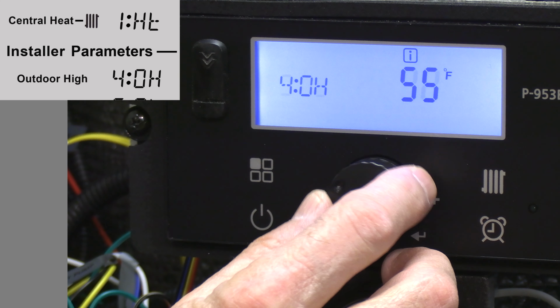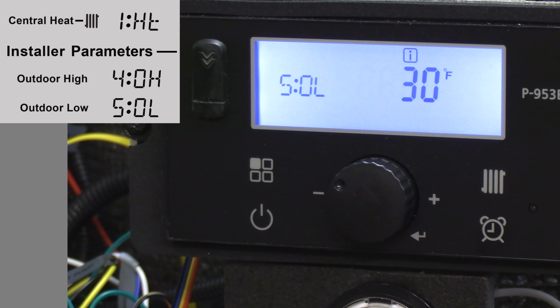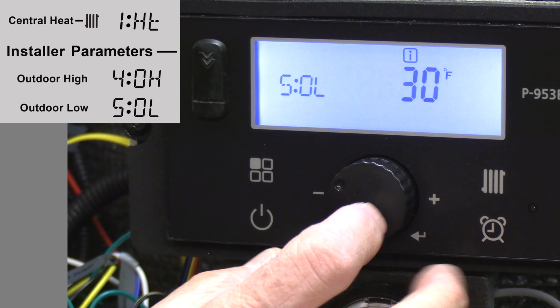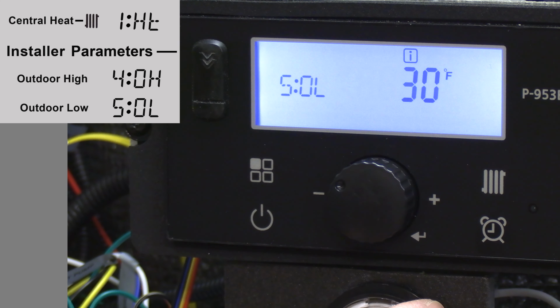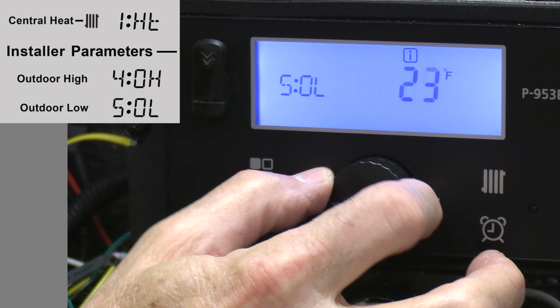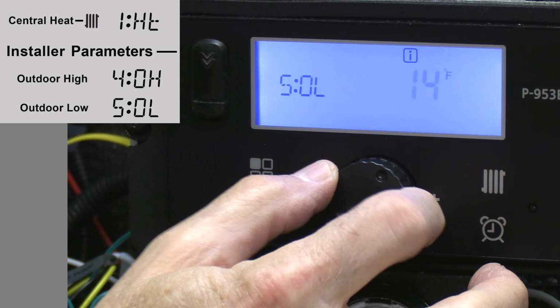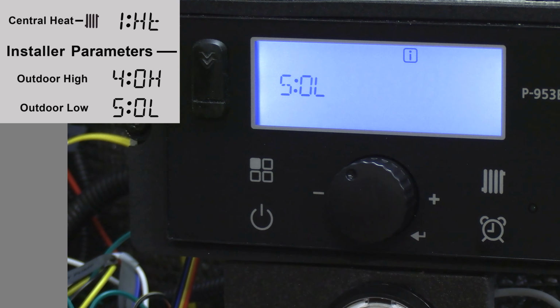Next, I'll go to parameter 5, which is my outdoor low. In here, we're defaulted for 30 degrees. And I'll use the example of New England or Boston, where the design day is 10 degrees. So instead of 30 degrees, at maybe 10 degrees, I'll deliver my 180 degree supply temperature. So make the adjustment, press the scroll, and now you can turn this down to your design day. And I use the example of 10 degrees above zero.